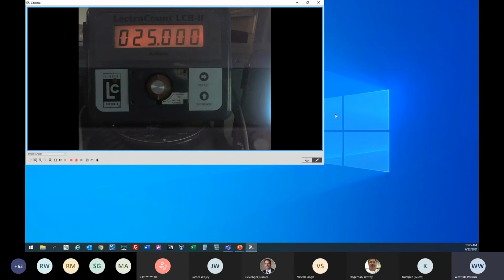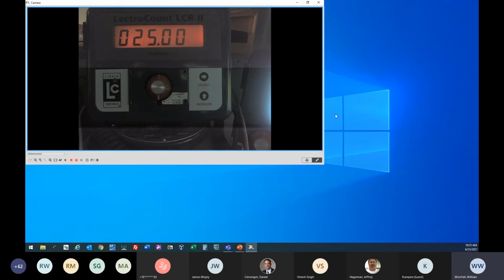And that last one. Now, just a bit of caution. If you do enter these digits wrong and you go to the next one, there's no way to go back to it. So be very careful when you're entering these numbers to make sure that they're correct before you hit the select key to move to the next one. Once you hit select on that last flashing one, that is entering your prover quantity into the register, and it's doing its calculations behind the scenes. So that's really as easy as it is using the front of the register for this.